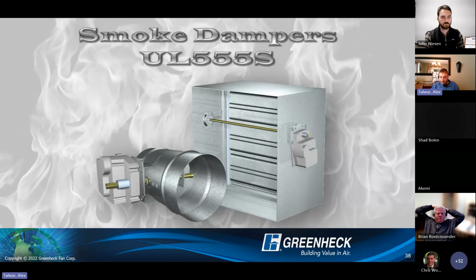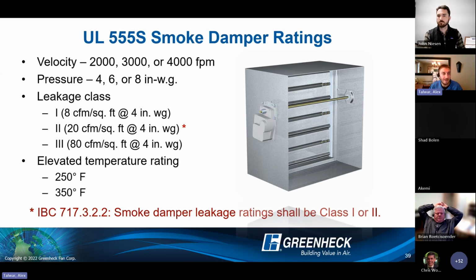So let's jump into smoke dampers. I do apologize if it seems like I'm going fast. I do have a lot of information to share today. So smoke damper products are typically configured in that multi-blade style that we see there. Here are the ratings. They're going to have the same velocity and pressure ratings that dynamic fire dampers do. This time, though, we are now introducing a leakage class with UL 555S smoke damper ratings. So class 1, 2, or 3. Class 1 is the best performance. Class 3 is the worst performance, and actually not even allowed by the International Building Code. So if you want an IBC qualified damper, it's got to be a UL 555S class 1 or 2 product. So you can see those leakage classes listed there.